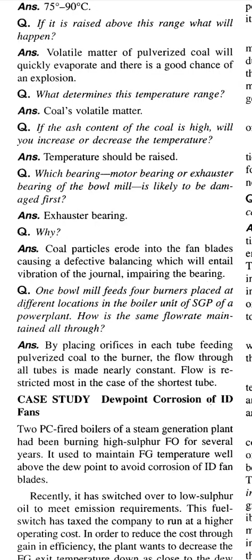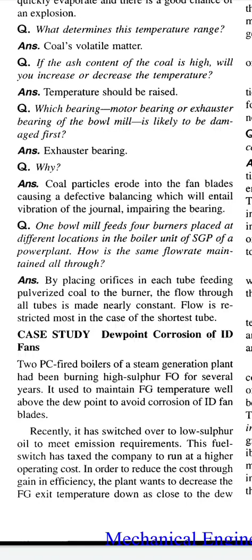Question: which bearing, motor bearing or exhauster bearing of the bowl mill, is likely to be damaged first? Answer: exhauster bearing. Question: why? Answer: coal particles erode the fan blades, causing defective balancing which will entail vibration of the journal, impairing the bearing.